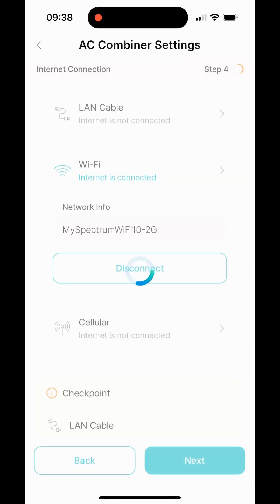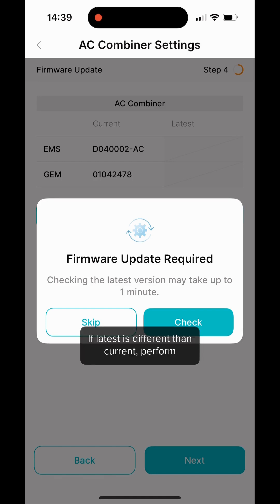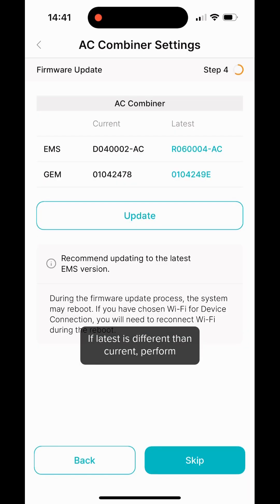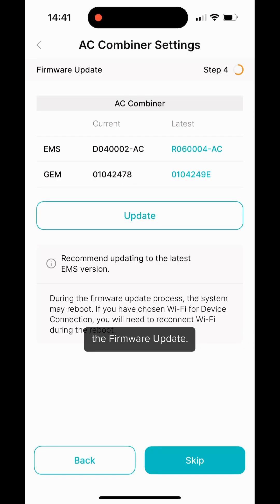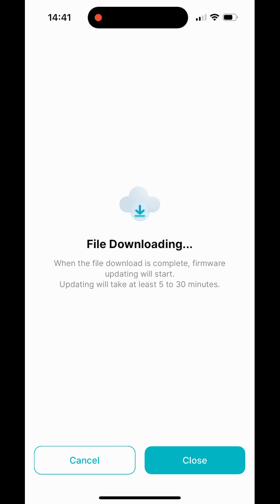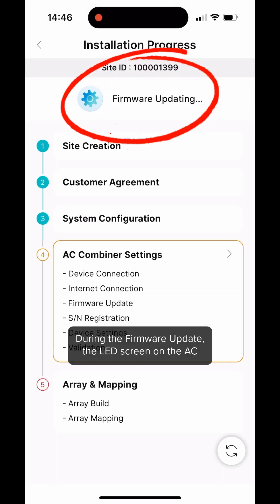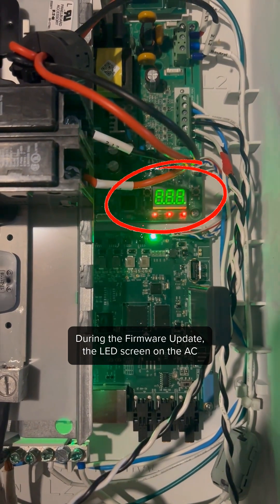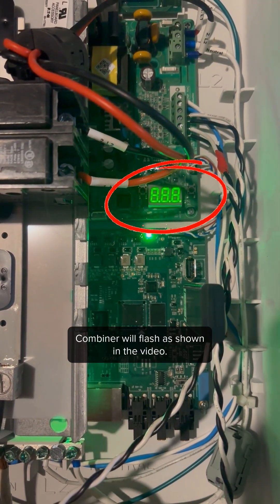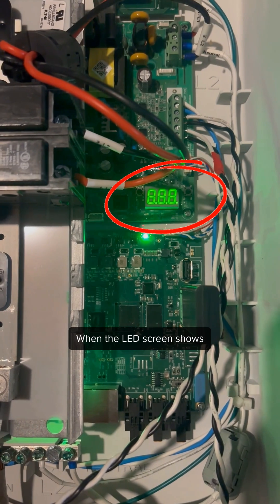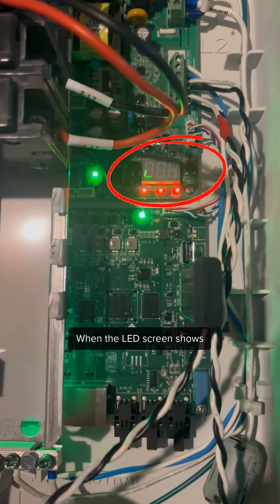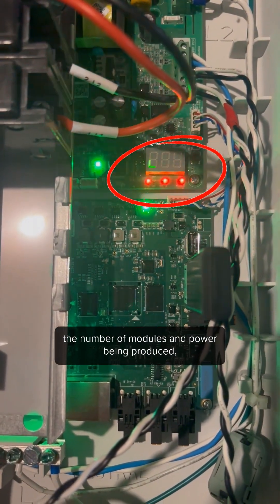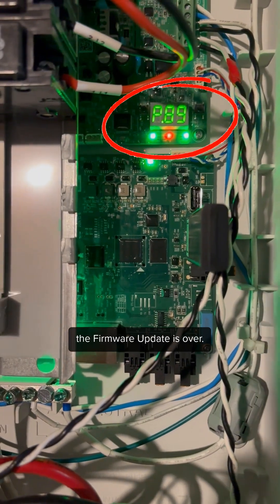Check for new firmware. If latest is different than current, perform the firmware update. During the firmware update, the LED screen on the AC Combiner will flash as shown in the video. When the LED screen shows the number of modules and power being produced, the firmware update is over.